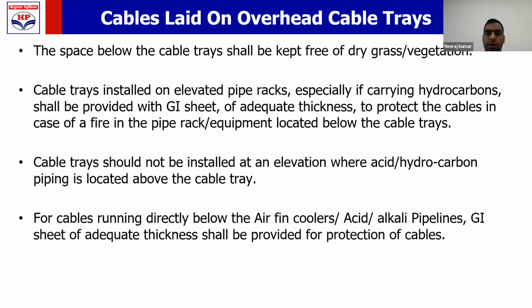Now, if you are laying cables in overhead trays, what needs to be done? ट्रे के नीचे ग्रास और वेजिटेशन कुछ है तो उसको वहां पे ग्रास और वेजिटेशन को होने से रोकना है। यदि आपकी जो ट्रेज है वो हाइड्रोकार्बन पाइप्स के साथ जा रही है, generally it is common that pipe rack and cable racks go side by side, one below another. Then in that case, to protect your cables from the fire, a GI sheet of adequate size should be provided for the cable trays. If your cable trays are running below the air fin coolers, acid alkali lines, then again you should provide a GI sheet as required for the cable running with hydrocarbon lines.